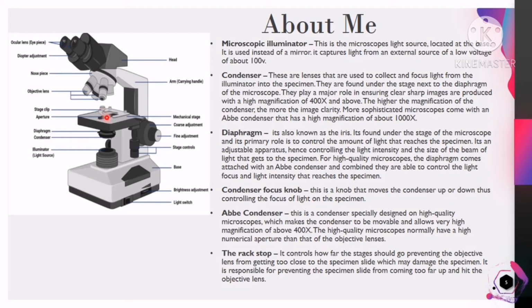Microscopic illuminator. Here it is. This is the microscope light source, and it's located at the base so that it is used instead of a mirror. It captures light from an external source of a low voltage of about 100 voltage. A condenser is here. As you can see, these are the lenses that are used to collect and focus light from the illuminator onto the specimen. They are found under the stage next to the diaphragm here of the microscope. They play a major role ensuring clear, sharp images are produced with a high magnification of 400 times and above. The higher the magnification of the condenser, the more the image clarity. More sophisticated microscopes come with an Abbe condenser that has a high magnification of about 1000 times.